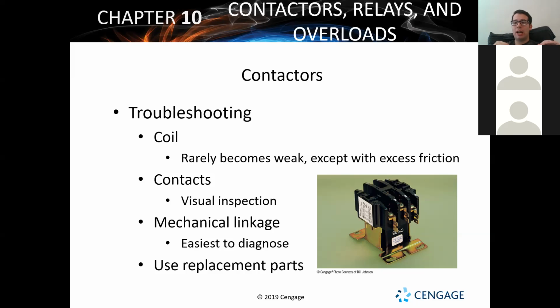Even without short cycling, arc welding can still occur just from wear and tear over time, if the contactor isn't cleaned regularly, if you're not making sure there's no debris, and if the outdoor control panel and access panel aren't protected.